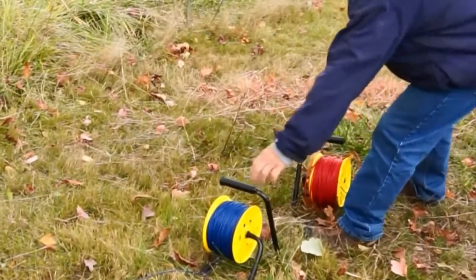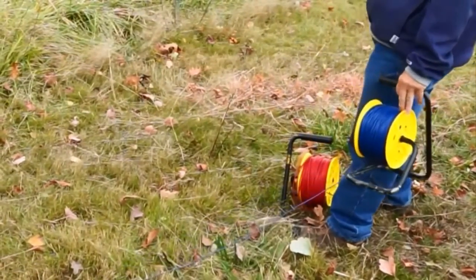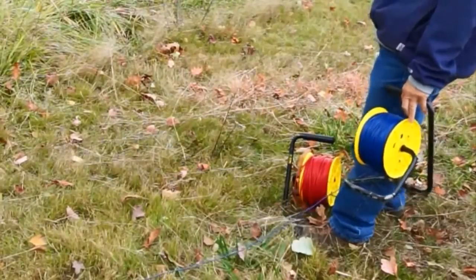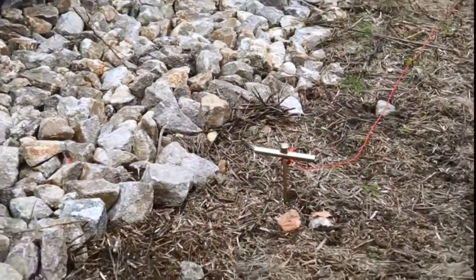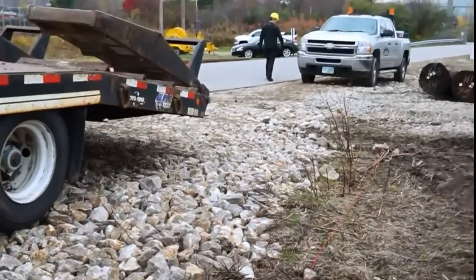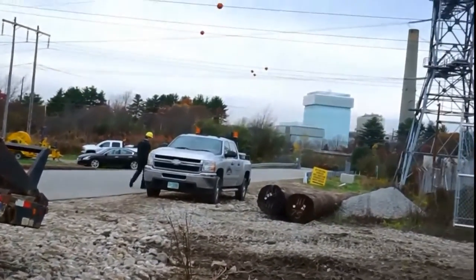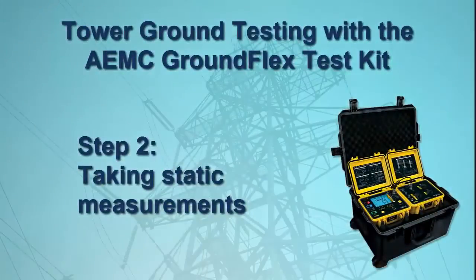Connect the electrodes to the Model 6472 using the red and blue leads that come with the kit. Ideally, the lead wires should be rolled out completely to avoid any inductance generated in the coils by the proximity of the transmission lines. We are now ready to take measurements.